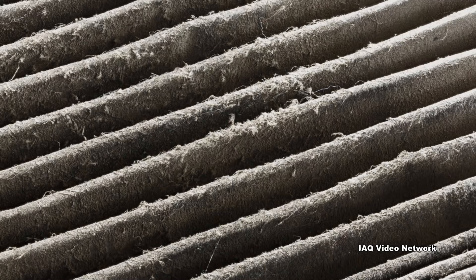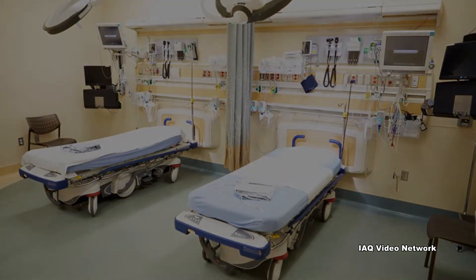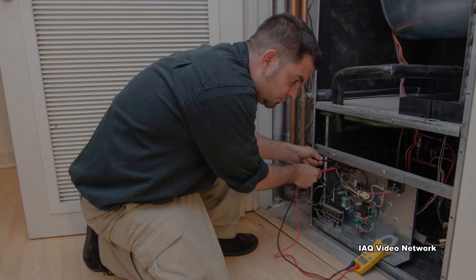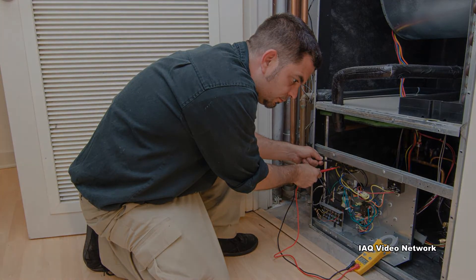The type of air filter can also play a role in how frequently it needs to be changed. Filters are given a minimum efficiency reporting value, or MERV, rated from 1 to 16. MERV ratings above 12 are typically used in special circumstances outside of a residential setting. The higher the MERV rating, the more effective it is at filtering airborne particles, but these denser filters may need to be changed more frequently. Also, if higher MERV filters cause too much resistance, a pressure drop in the HVAC system could lead to problems.